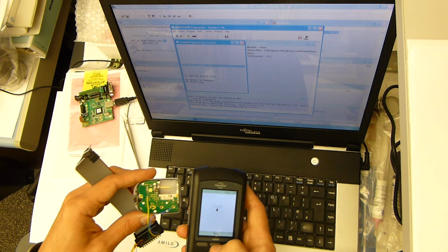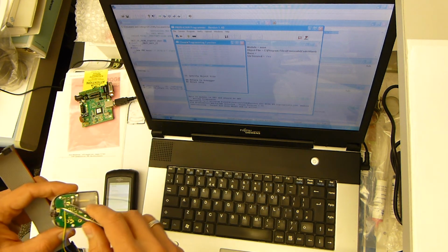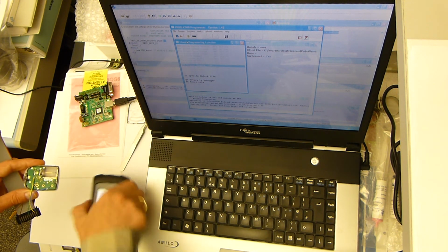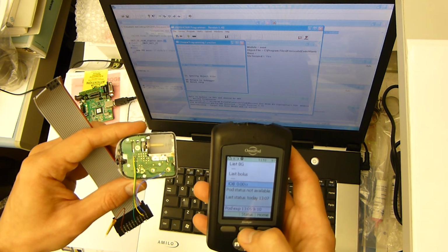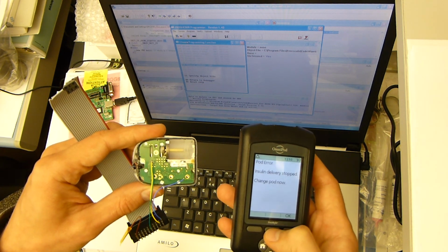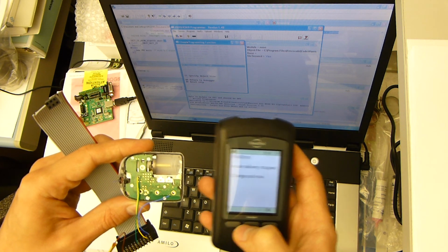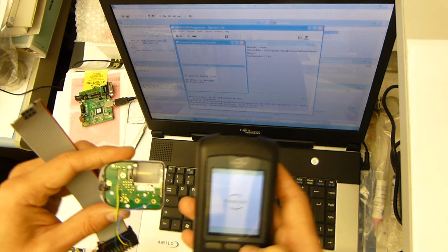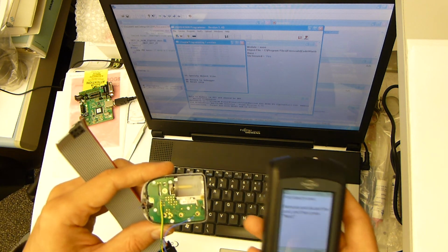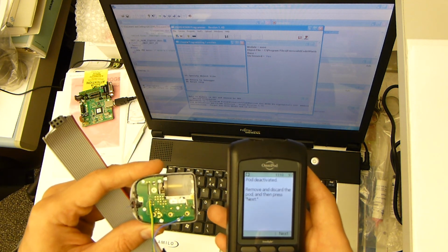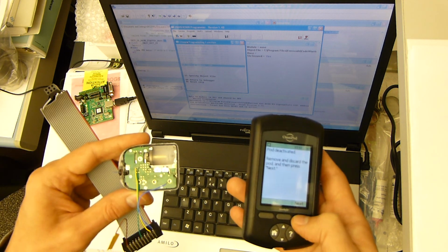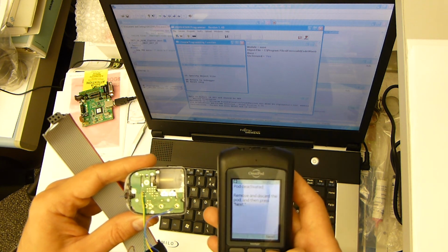You see, there's a communication error. And if we try to reset the pod, it will go into constant beep. And you see the PDM controller tells us that there's an error with the pod, insulin delivery stopped. So we need to deactivate the pod and either reprogram it or use a new one. So now it's stopped beeping, pod is deactivated, and we can no longer use it, but we can reflash the firmware and test it again.